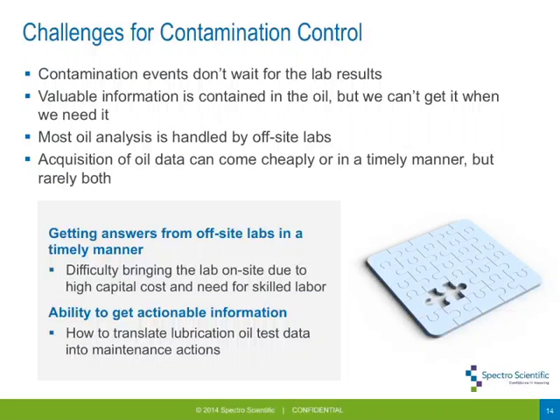So what are the challenges at the moment for contamination control? Most people still send their oil samples out to labs — using their oil supplier or an independent lab. The problem is that contamination events don't wait for lab results; they continue to occur all the time. The challenge is that maintainers can actually detect most of these problems using current marketplace technologies at the point of use, right at the machine level. If they can detect it right there, they get actionable information and can head off the problem before it becomes a big issue.